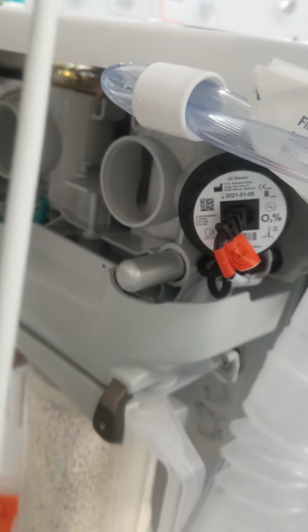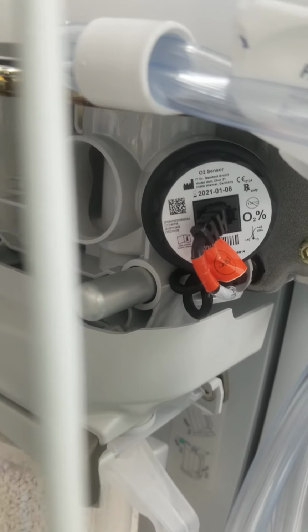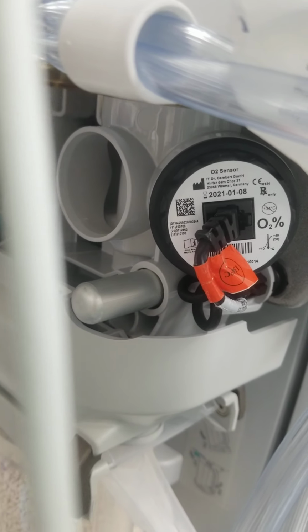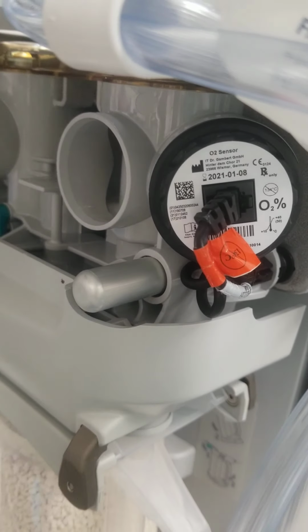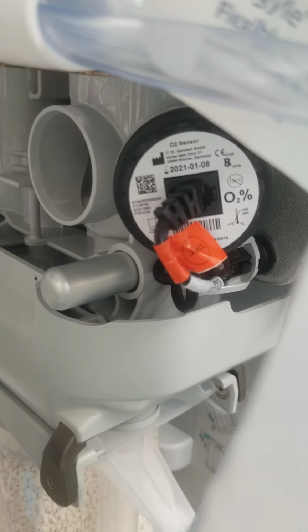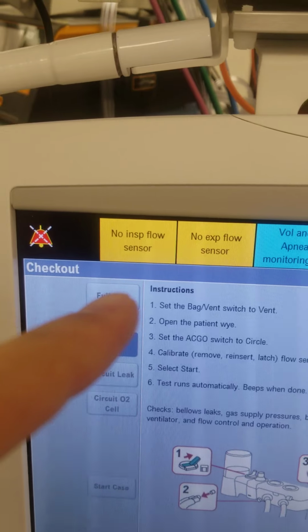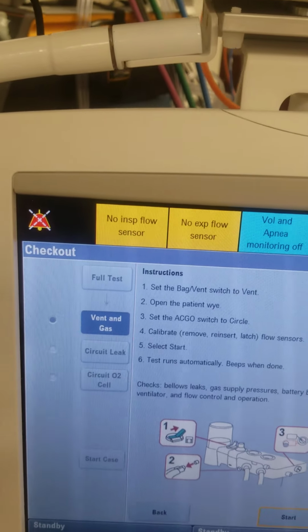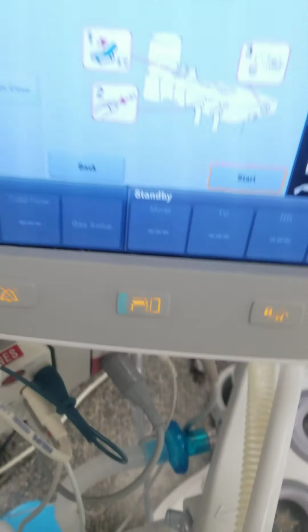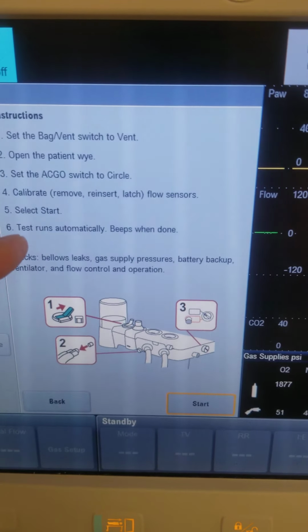You don't need to fully remove this, but I'm going to remove it and then just show you that that device right there that has like the telephone wire hooked up to, that's your oxygen sensor. So that's how you actually calibrate your 21% and your 100% oxygen. Whenever that doesn't calibrate well, you can manually calibrate it by taking this out. So let's hook that back in. We only need to remove this just a little bit. Okay. Once you see the no inspiratory flow, no expiratory flow sensor, that means you've done your flow sensors. So then you can pop this back in and you can lock it. So we've done that part. So we can go back to doing what we talked about.